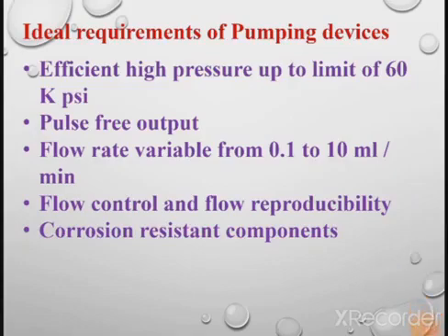Next, the ideal requirements for the pumping device. The pumping device we are using is to provide high pressure, and that's why the pumping device should provide the high pressure as required, and here the limit is 60 kpsi. Whatever output we are getting from the pump, it should be pulse free.